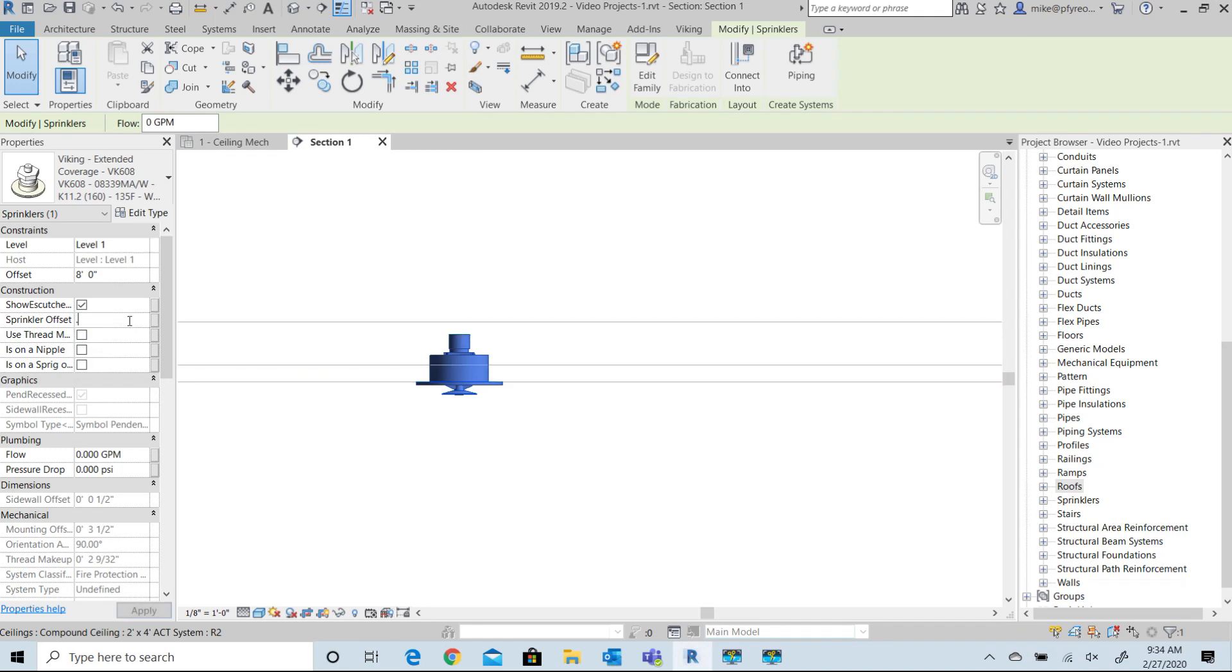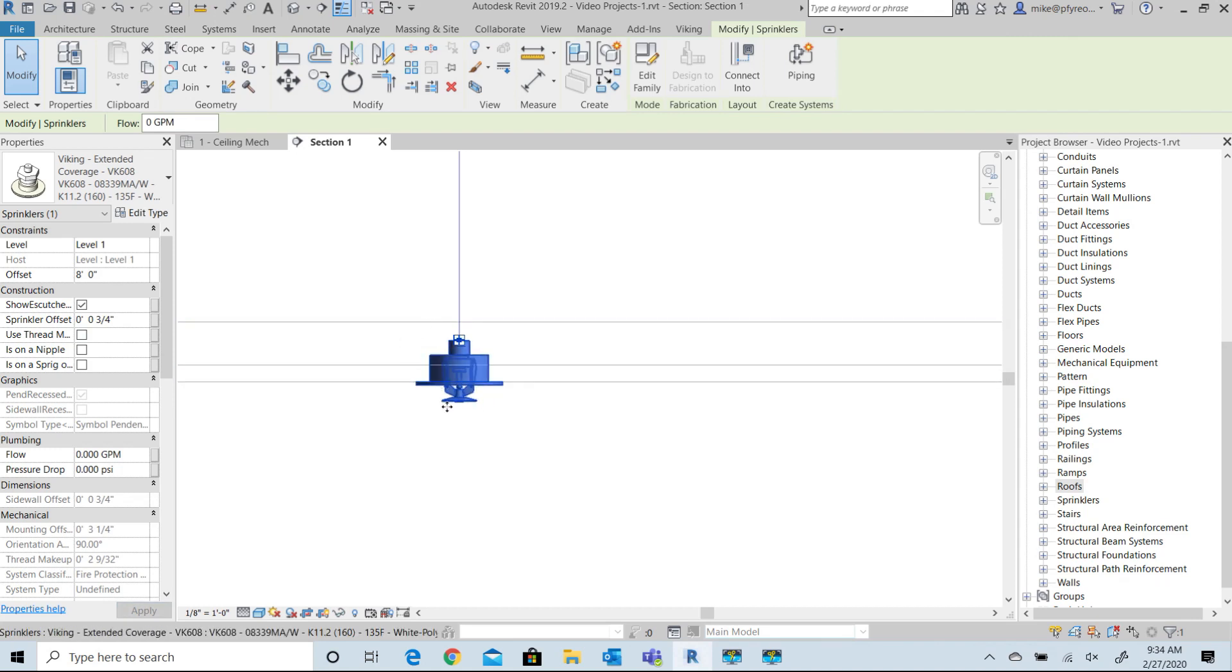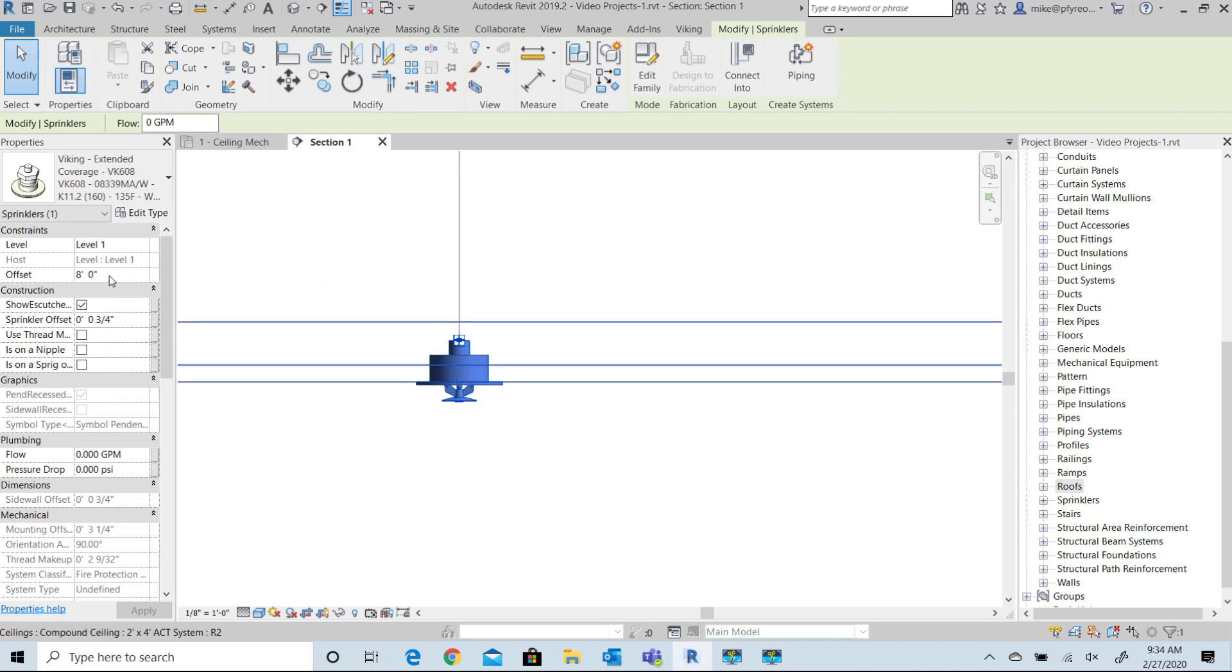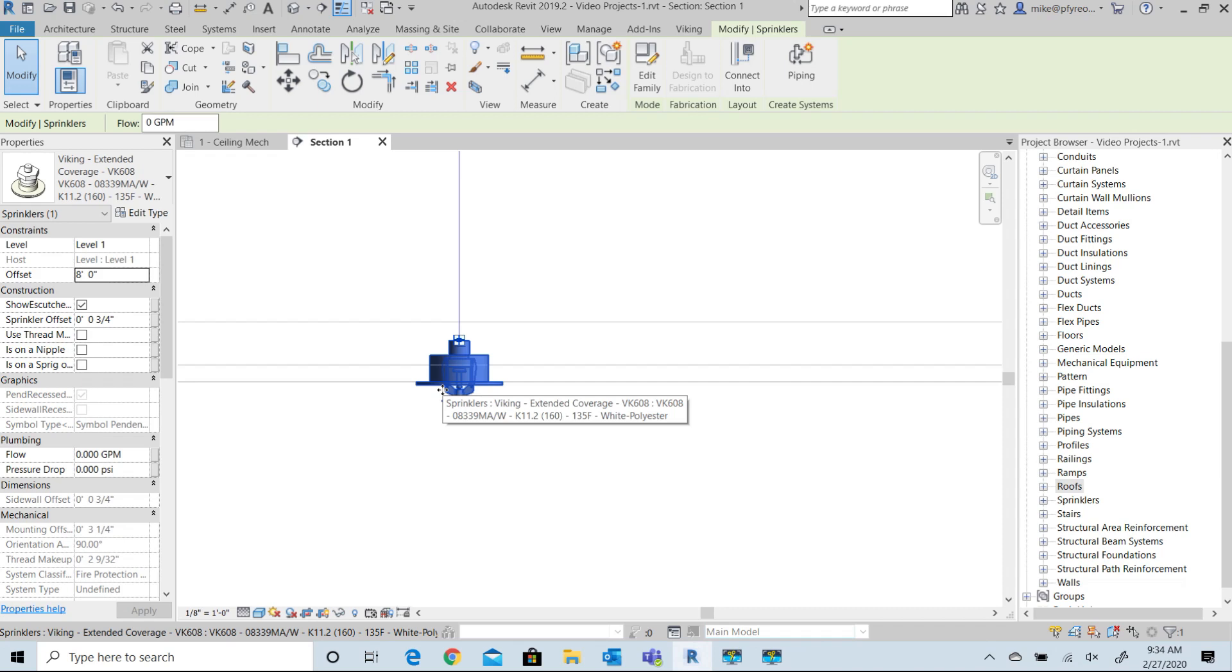If you need to change the deflector adjustments further, just change the value in the sprinkler offset. Notice that the offset value for the sprinkler is still at eight feet for the Revit default. This option is designed to limit the amount of calculations that you need to do to properly elevate the sprinkler.